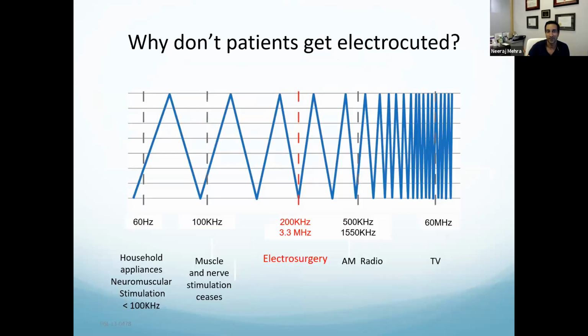Slightly trick question, but it has to do with the frequency. Electrosurgical energy generates the energy in the radio frequency range. Just like we have Wi-Fi and all these signals going through the air, we're not getting electrocuted by all this energy, because it's at a frequency that's not causing muscle and nervous stimulation. It's the same thing with electrosurgical energy - it's operating at a higher frequency range than that which causes muscle and nerve stimulation.